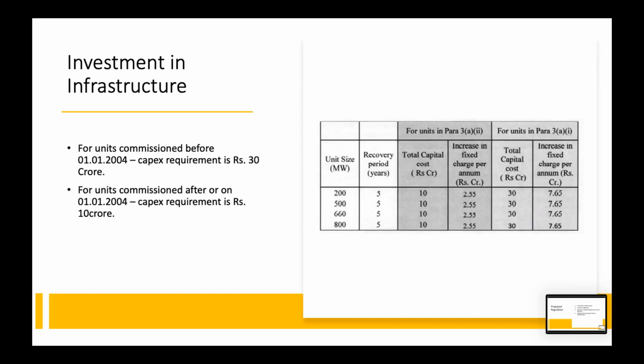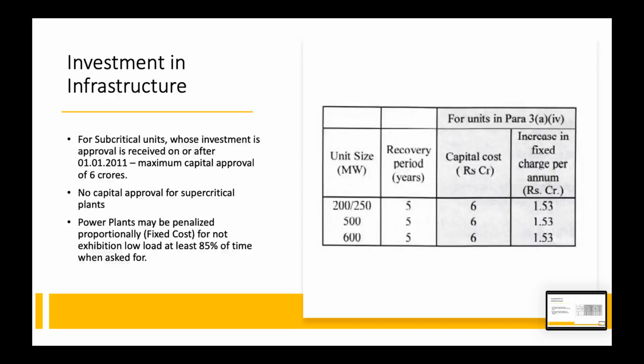In the next criteria, the classification has been based on subcritical or supercritical units. For the units which have been commissioned after 1st January 2011 or on the date of 1st January 2011, if they are subcritical in nature, then a capital cost of rupees 6 crore has been considered as the requirement of investment for the units to run at 40% technical minimum. No provision of capital cost has been incorporated for supercritical units whose letter of approval date is after 1st January 2011.